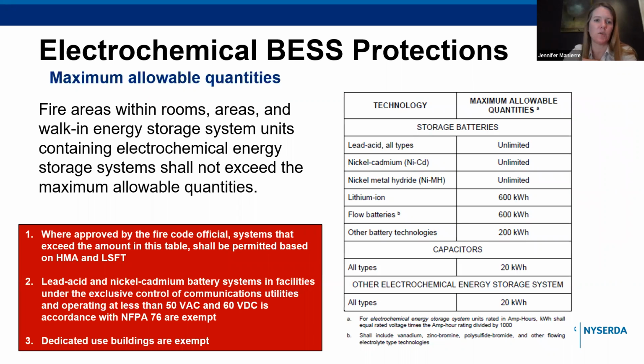Okay, maximum allowable quantities. So this chart in the code basically just shows what it says, the maximum allowable quantity based on the different technology types. So lead acid batteries, the first one on the list here, there is no maximum quantity that's allowed for any one system for those. However, again, we're going to be mostly focusing on lithium ion. That's what you're most likely to see. The maximum allowable quantity for those is 600 kilowatt hours.